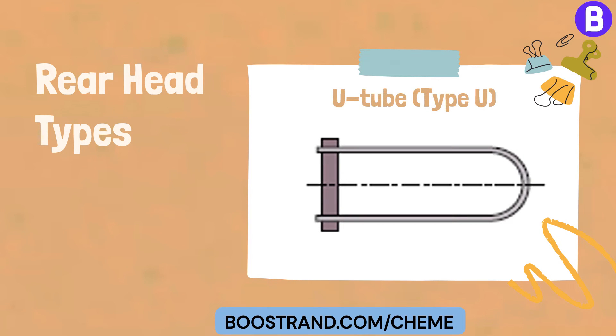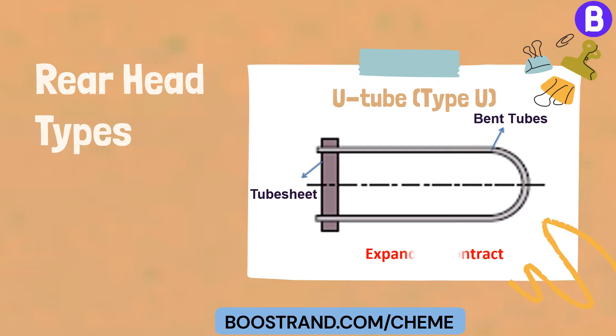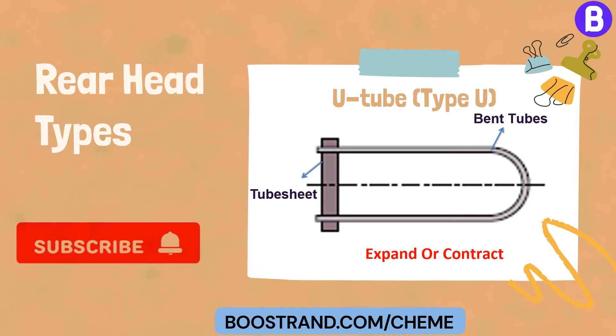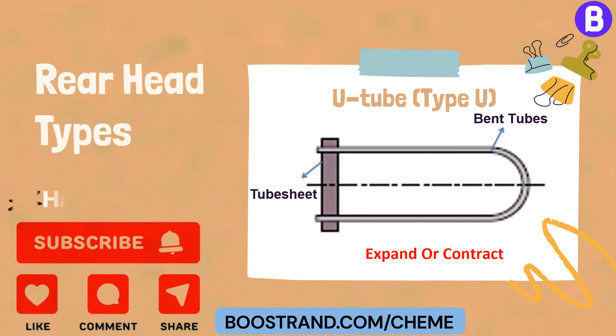U-tube, Type U: this design has a single tube sheet and bent tubes, allowing the bundle to expand or contract to handle stress differentials. However, the tube interior can be difficult to clean due to the U-bend.